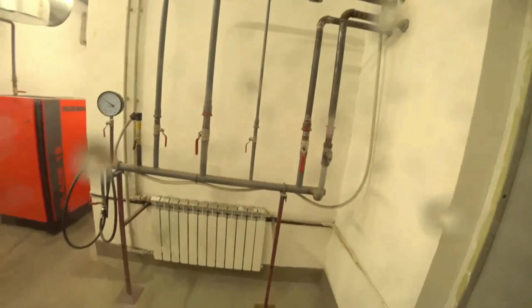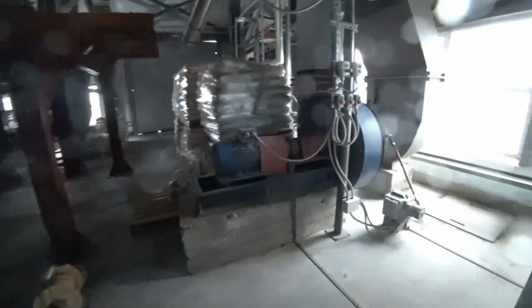The room is equipped with supply and exhaust ventilation. Compressed air is distributed in the manifold to all consumers. In front of you is a Ukrainian-made primary air fan. The fan is equipped with a single-turn electric mechanism for automatic regulation of the productivity and pressure of the primary air. Primary air is supplied under the inclined pushing grate.